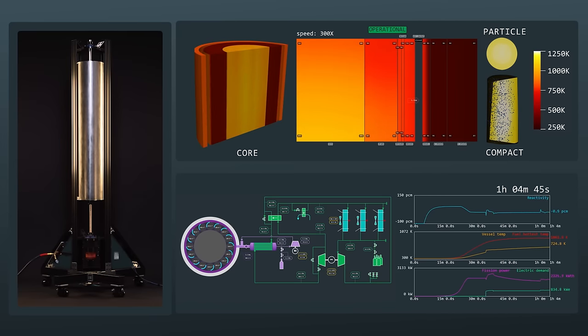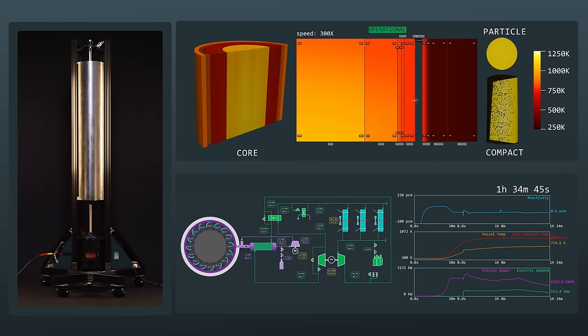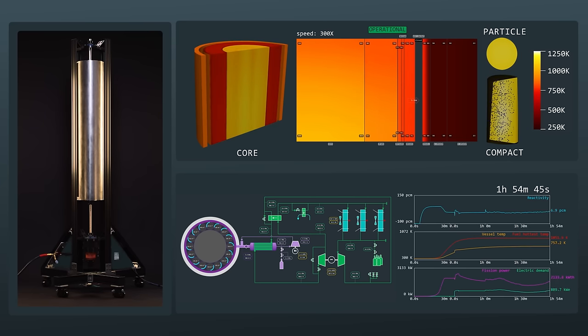The turbo machinery ramps up to speed as the core reaches target temperature, and a circuit breaker connects the microgrid electrical load. Unlike traditional nuclear power plants, Kaleidos is capable of rapid load throttling or efficiently following a fluctuating electric demand. This is accomplished by adjusting the machinery shaft speed, the helium mass flow rate, and by continuously moving the control drums to modulate core heat generation.